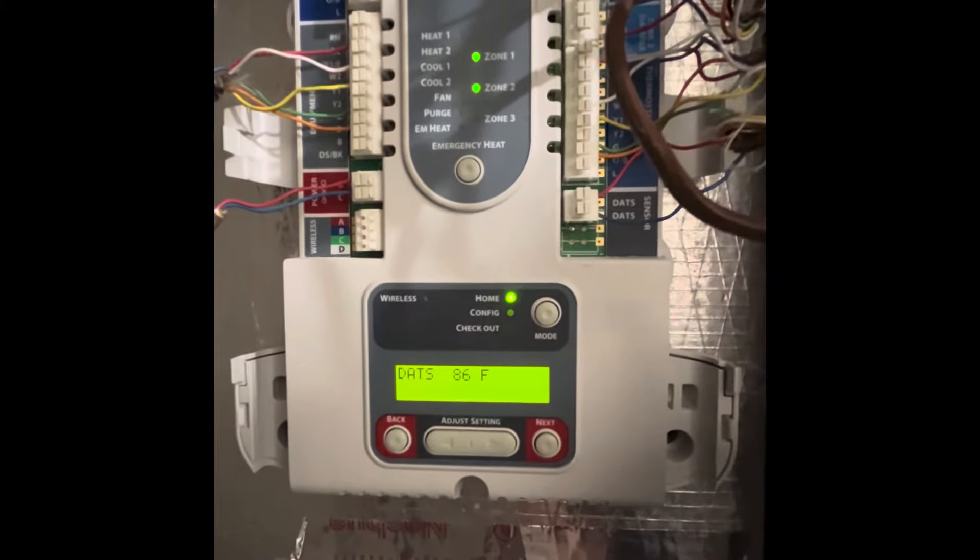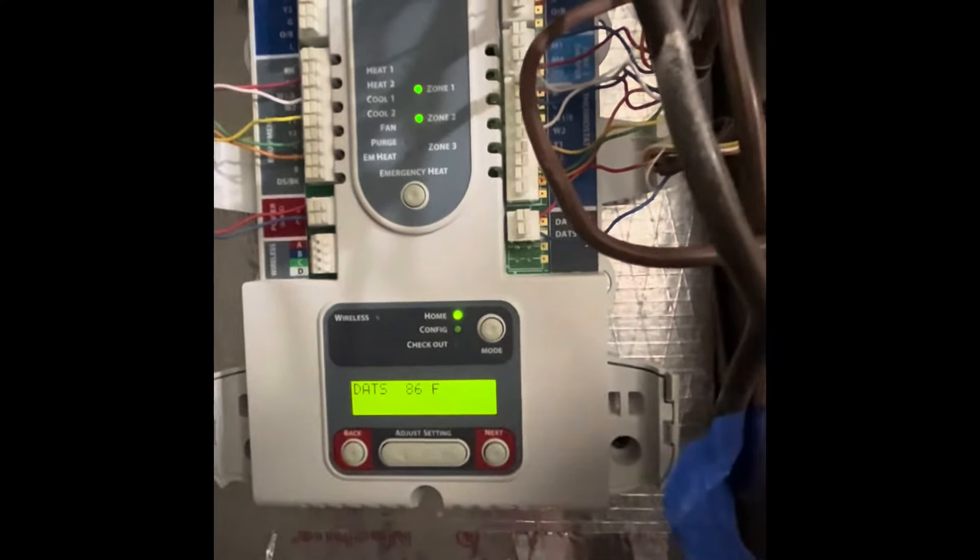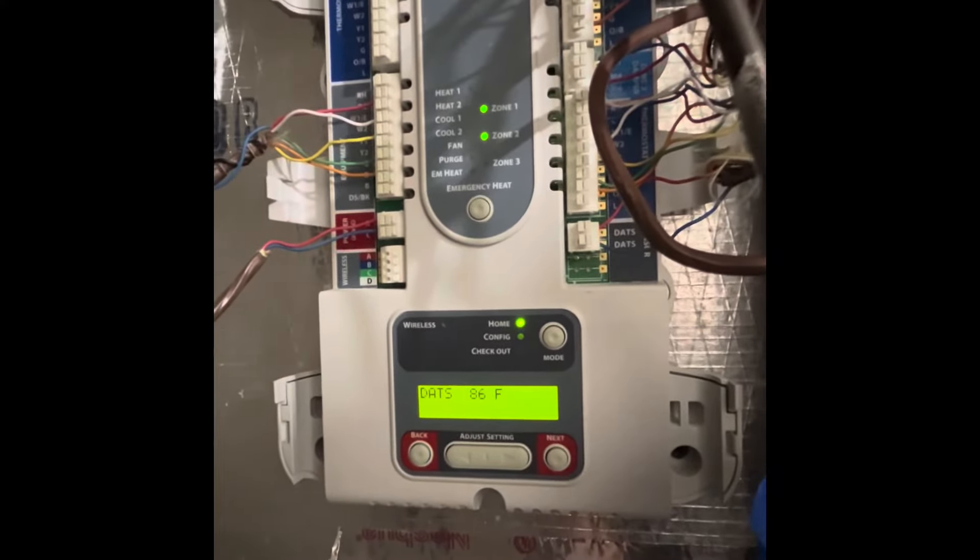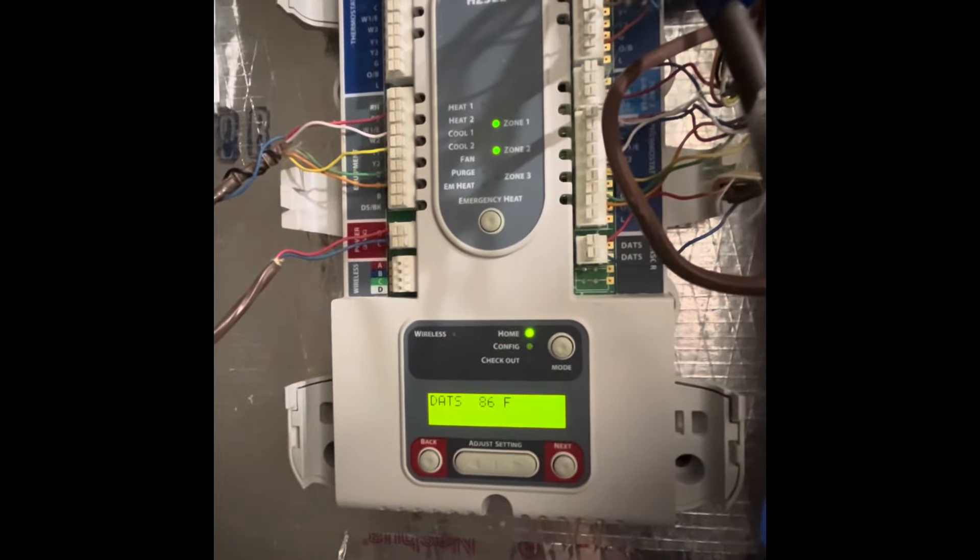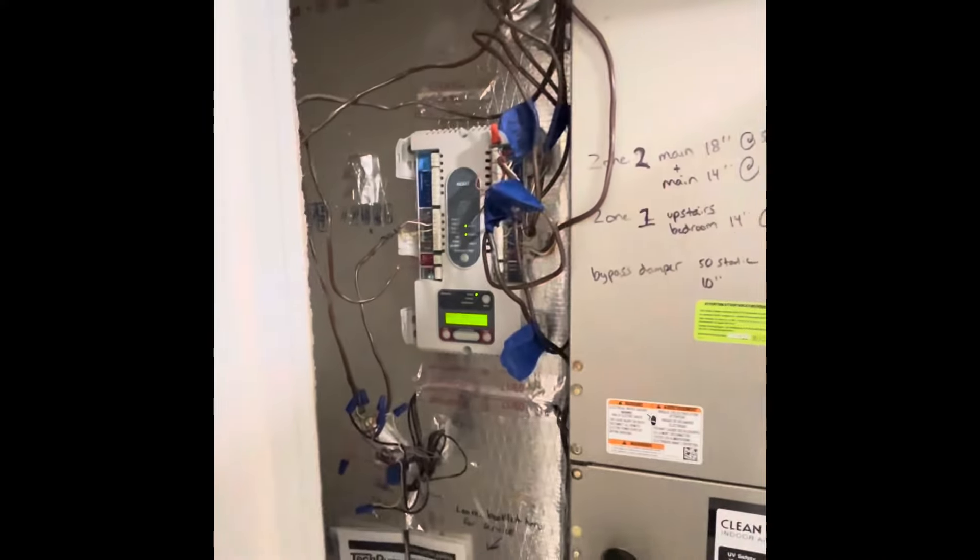So if you do want to bypass it, just unhook it. Pull these two wires out. It'll say 'DATS not present' and your system will run fine. You don't even have to bother hooking up a new sensor. That is the most common problem with a Honeywell zone panel.